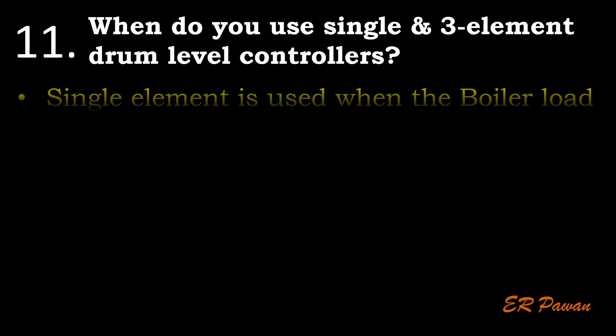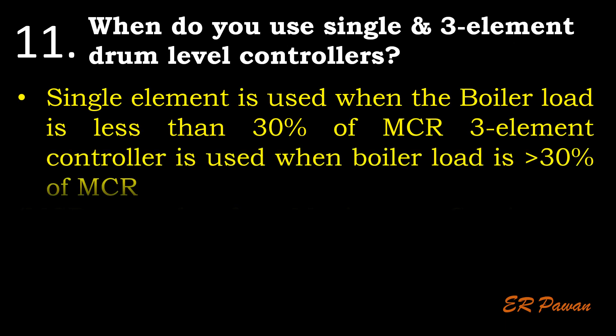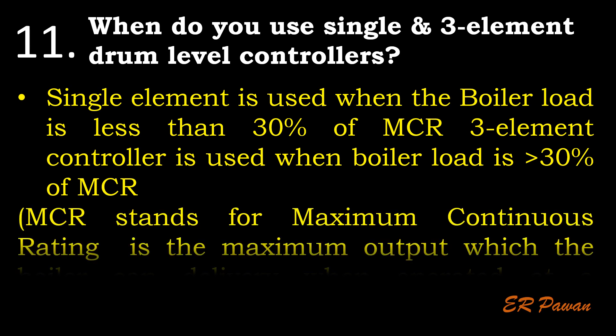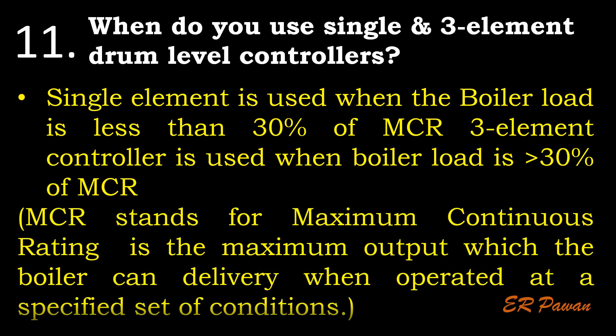Question 11: When do you use single and three element drum level controllers? Single element is used when the boiler load is less than 30% of MCR. Three element controller is used when boiler load is greater than 30% of MCR. MCR stands for Maximum Continuous Rating — the maximum output which the boiler can deliver when operated at a specified set of conditions.